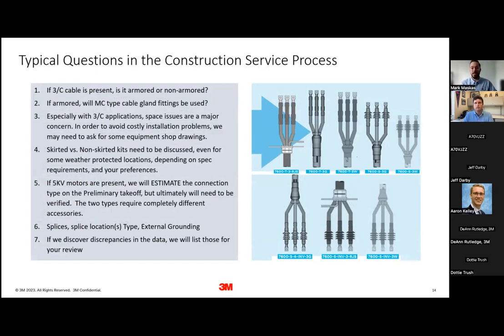We might need to ask for equipment shop drawings to avoid costly installation problems. Skirted versus non-skirted, outdoor versus indoor terminations, we'll discuss that as well. And the splice location, splice type, external grounding, connection types for the 5 kV motor. These are things we may have questions on, which is why it's good to have an open line of communication between us and the designated contact person for your project.